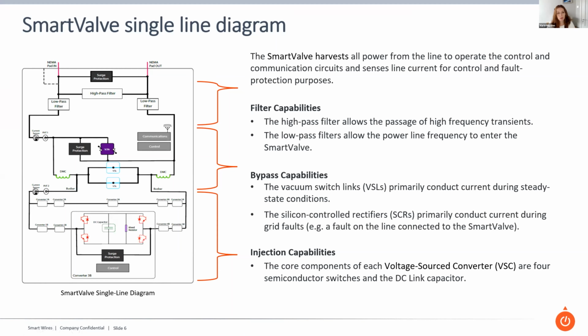When we are in injection mode, one of the limitations of IGBTs is how much current they can handle. The IGBTs we use can handle up to 1800 amps, so that's a significant amount of current to put through IGBTs, and in fact over 2000 amps in overload conditions for a few hours. But they're not designed to carry high levels of fault current, the sort of 63,000 amps we talked about earlier on. And so we use silicon controlled rectifiers to handle fault current, and we use a very sophisticated, speedy fault current detection system that activates or fires these SCRs within about 1 microsecond of a fault being detected, or I should say an overcurrent being detected, to be honest.